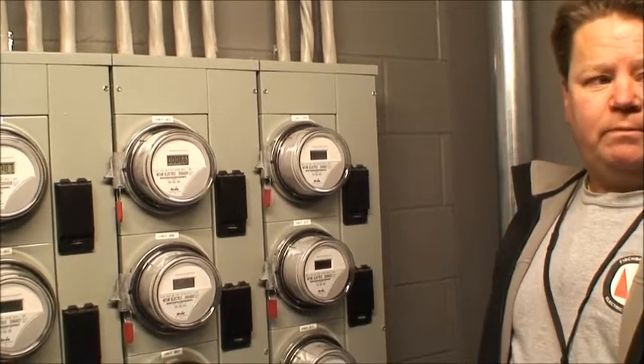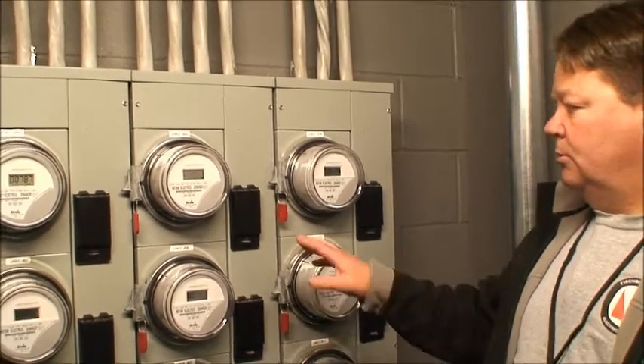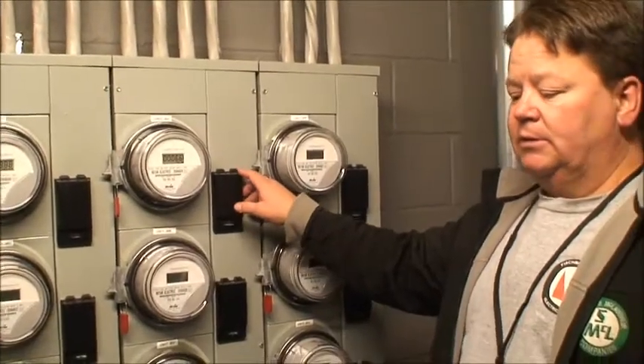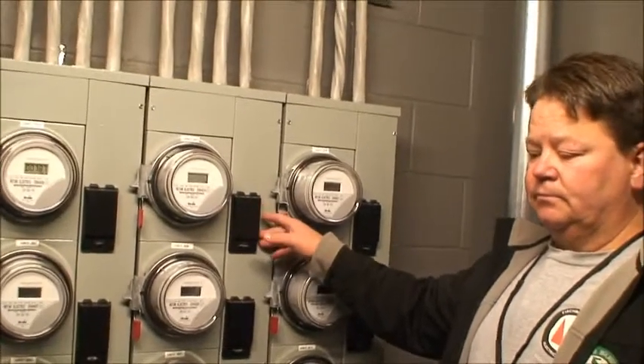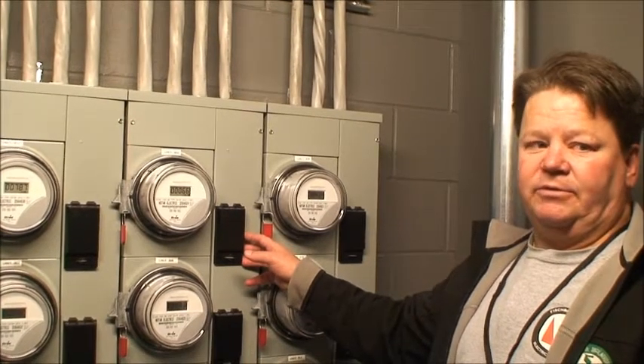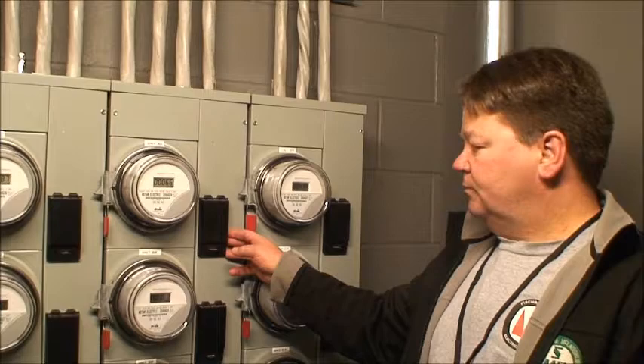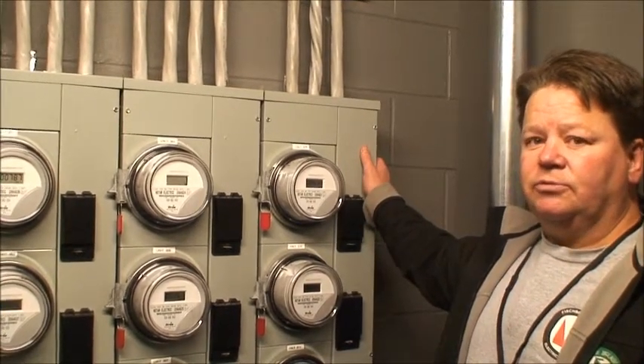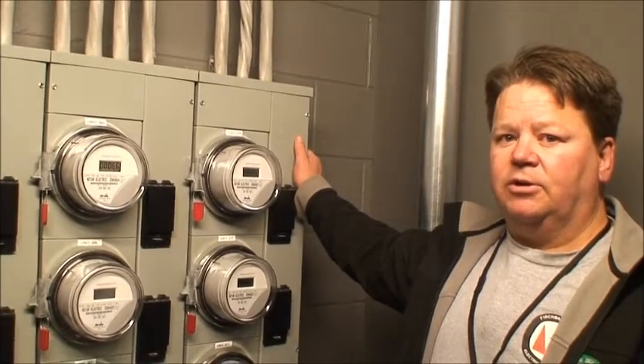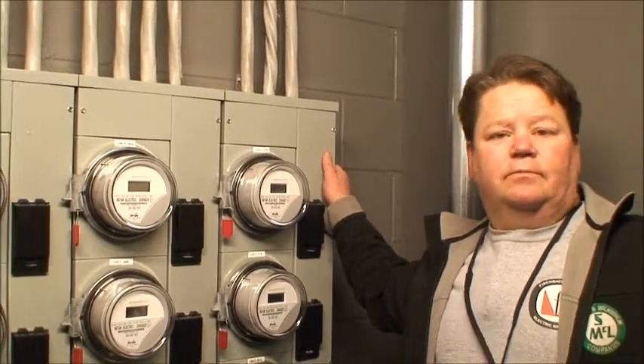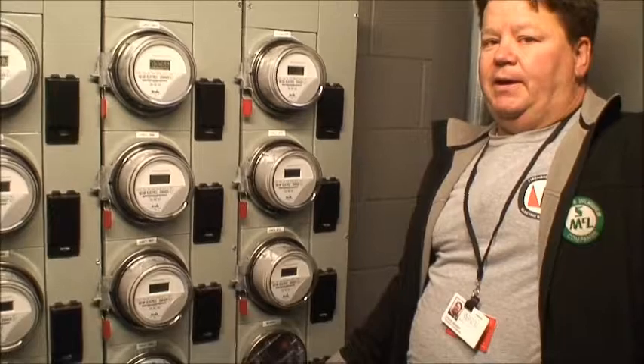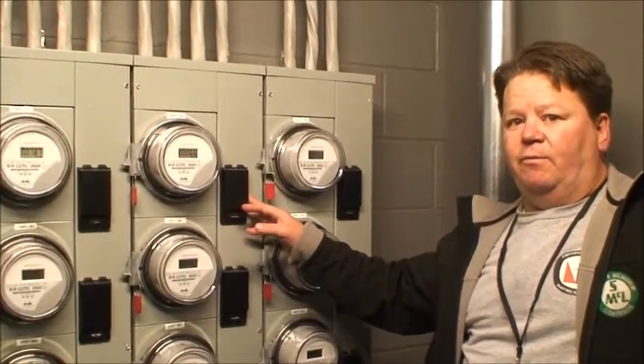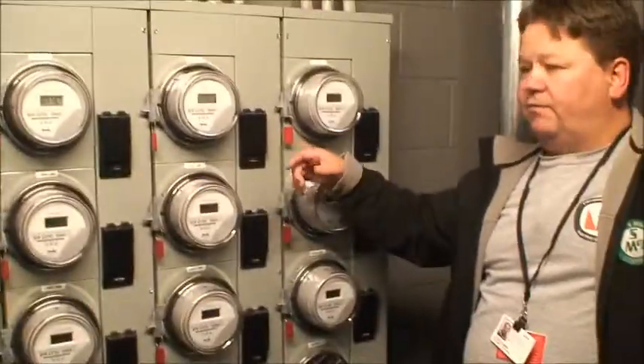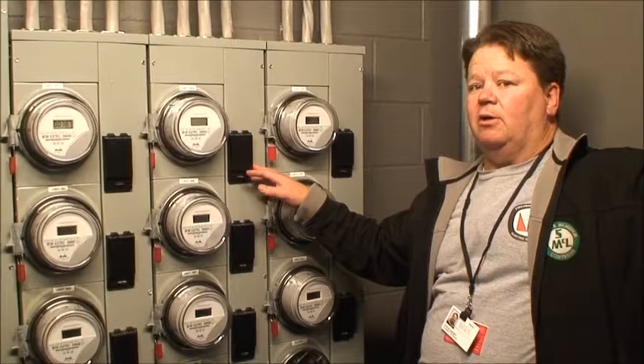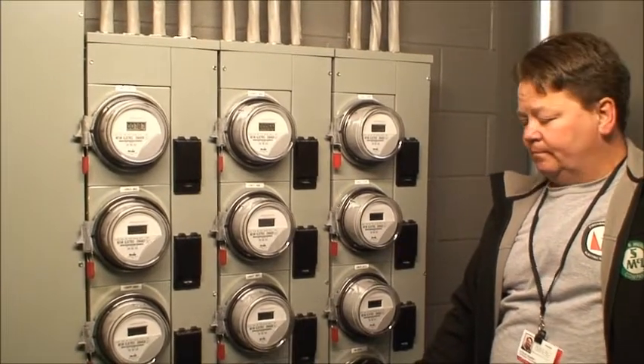Okay. So if they bust a breaker in the middle of the night, we'd have to come out to reset it? If they had tripped the main to here, yes, you'd have to reset it here. Okay. The demand on these apartments, I don't think you'd ever trip a main. Okay. Well, let's say they busted a light fixture and you had to replace it. You could shut off that breaker, the individual circuit within the unit. You can shut off the lighting circuit. Or if there was something major, you could shut the whole unit down here. If you needed to open up the panel, you should shut it down here. If you need to open that panel for whatever reason, we don't do any live work. Right. If you would call us, we'd come out, shut down, then open up the panel, then investigate the problem. If it was downline, we could turn it back on and investigate downline from individual breakers. Yep, okay, that makes sense.